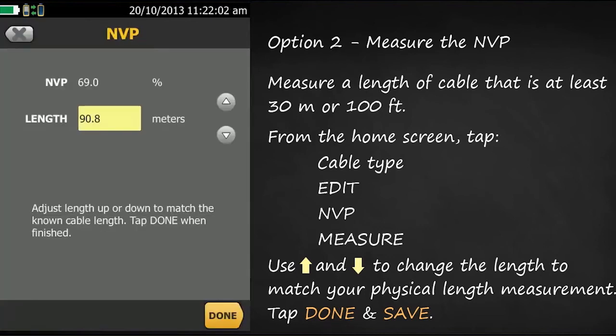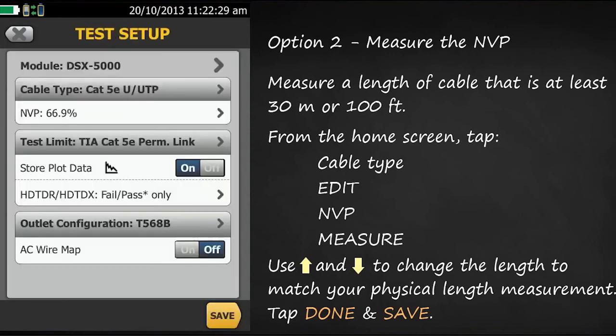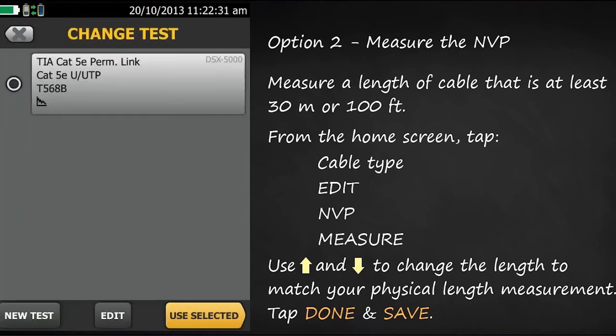With my NVP set at 69%, the tester thinks the length is 90.8 meters. Actually, the length of my link is 88 meters. So I'm going to change the length so it says 88 meters, and you'll notice the NVP value is also changing at the same time. The measured NVP of this cable is 66.9%. Tap done, save, and use selected.